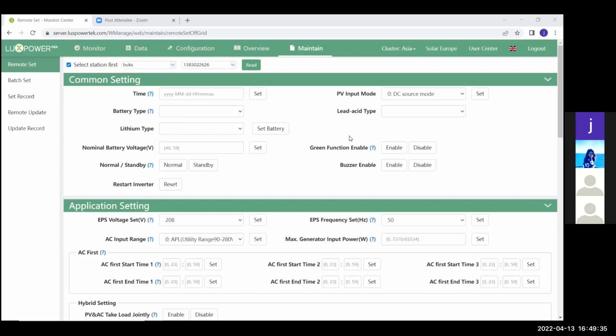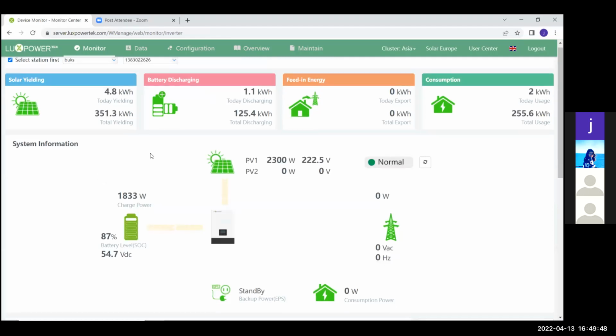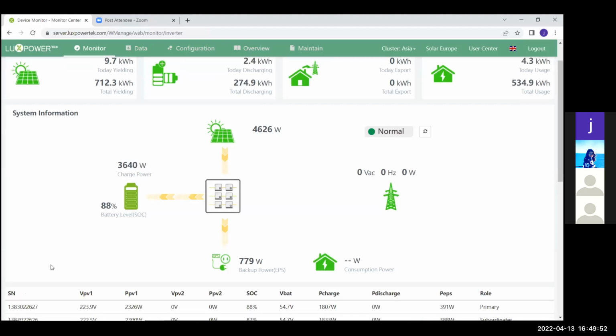Where can you see that the BMS comms is active? Okay, for you to see if your BMS communication is active, first of all, if your inverter is not communicating at all, it won't show you anything of percentage or volts. It will be like your system doesn't have any battery. It will also tell you here communication fail. If you click on the battery, you can see the Shoto battery is communicating 100%. There's 2 of them in parallel, and the BMS will tell the inverter, there's my charge limit at 50 amps per battery, so that's 100 in total, and there's the discharge limit as well. So if your BMS is communicating correctly, then you'll see this information here. I hope that answers your question.